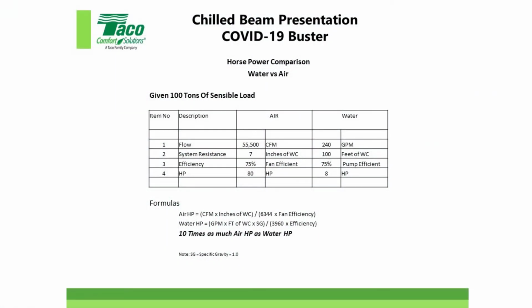And this just shows you, if you start going through the formulas, and I don't really like to go through the formulas, they're up here, you can take a picture of it, but 10 times as much air horsepower as water horsepower to cool that room, to cool that zone. So that's a big savings right there. So, Taco's a manufacturer of HVAC hydronic equipment. We like to talk hydronics as much as we can. And if you can show people how to save money, save energy, less horsepower, and get the ball rolling in that direction, that's what we like to do. And we think it's a very good alternative to other types of systems that are out there.